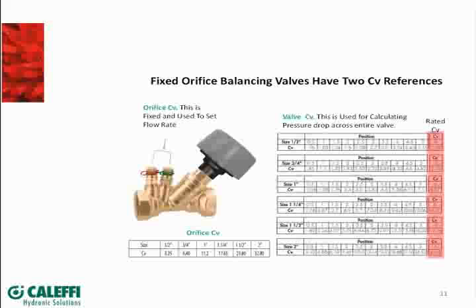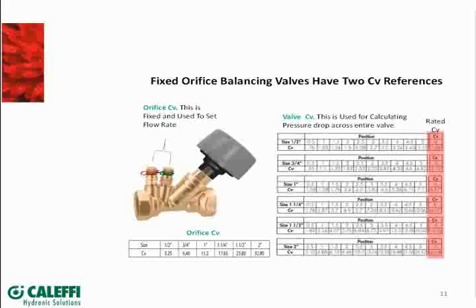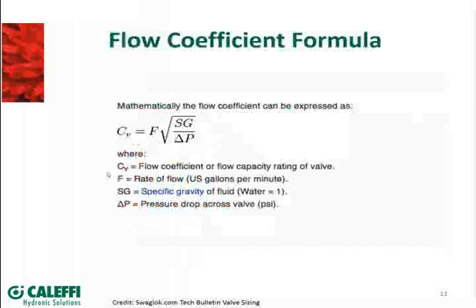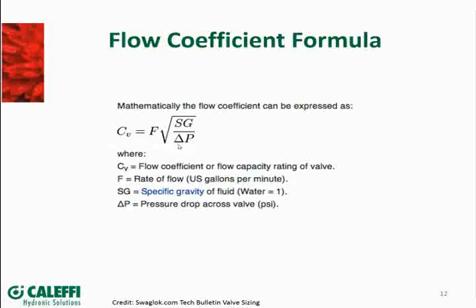Hopefully that clears up the two different types of valves and how they perform and adjust differently. Getting back to the formula — CV equals the flow rate F in U.S. gallons per minute, multiplied by the square root of SG (specific gravity, which is one for water) divided by delta P, which is the pressure drop across the valve measured across those ports. I'll show you the test apparatus that is the standard for this type of testing that we use to come up with these numbers.